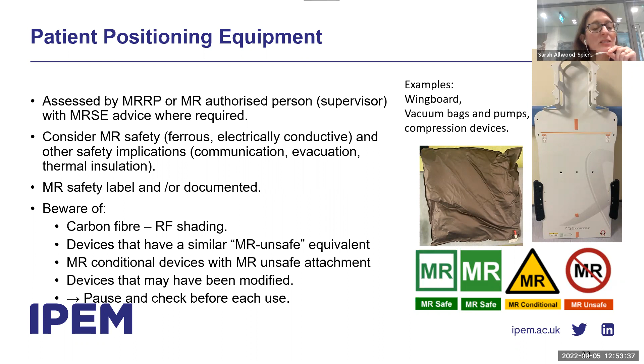Any MR conditional devices that might have an unsafe attachment, or any devices that might have been modified. It's important prior to entering the scan room that all MR authorized persons pause and check that this is the device that is MR conditional or safe, and check that with a magnet if needed. All departments should have a strong handheld magnet to test items to be taken into the MR environment.